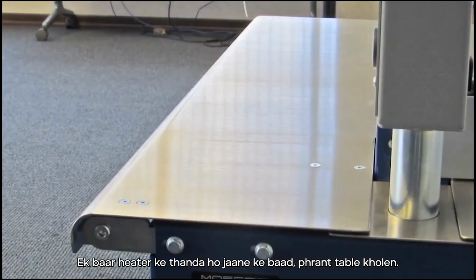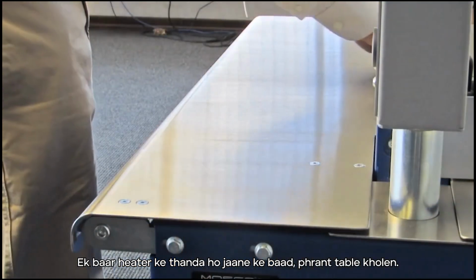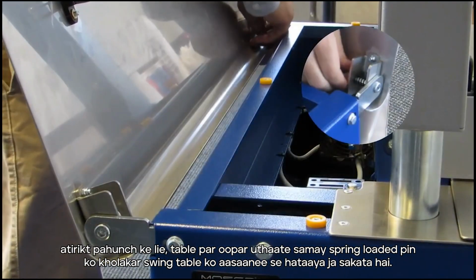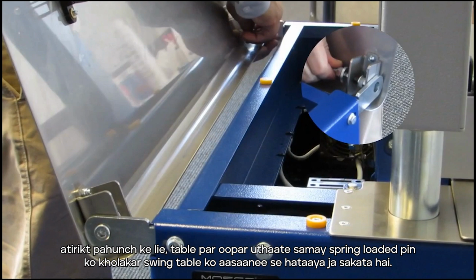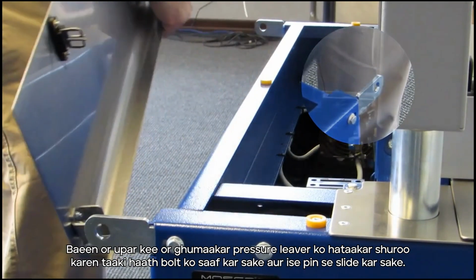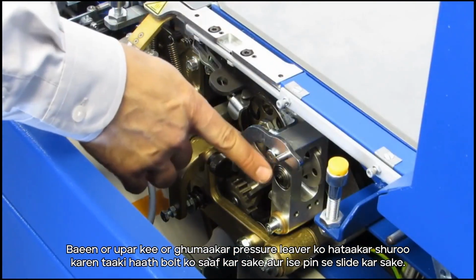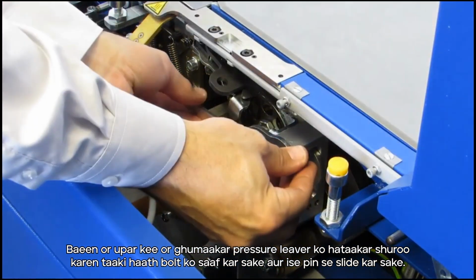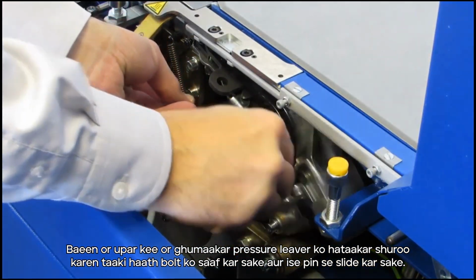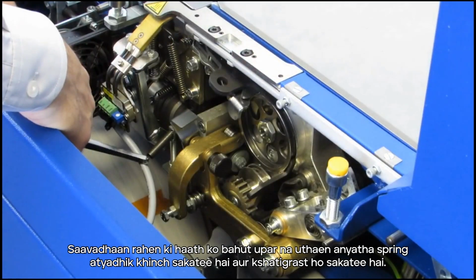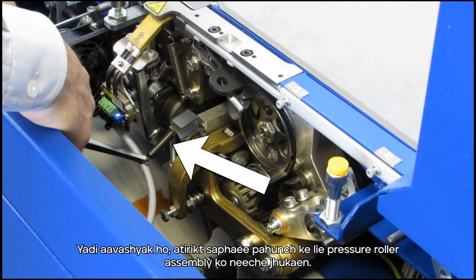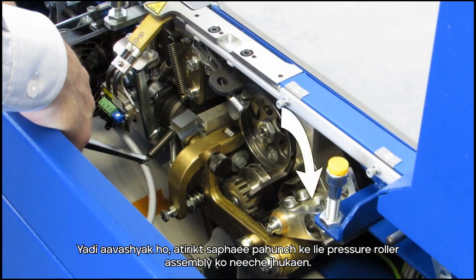Once the heater has cooled down, open the front table. For additional access, the swing table can be easily removed by disengaging the spring-loaded pin while lifting up on the table. Begin by removing the pressure lever by pivoting the left side up so the arm can clear the bolt and slide it off the pin. Be careful not to lift the arm too high or the spring can become overstretched and damaged. If necessary, tilt the pressure roller assembly down for additional cleaning access.